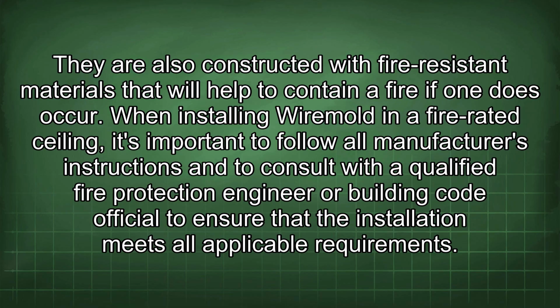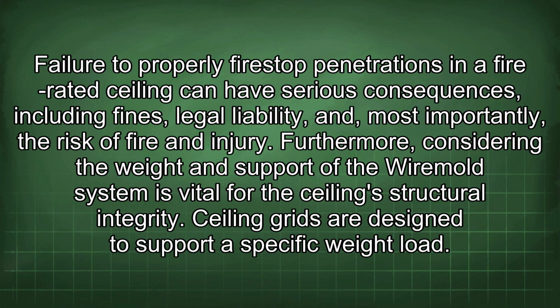When installing Wiremold in a fire-rated ceiling, it's important to follow all manufacturer's instructions and to consult with a qualified fire protection engineer or building code official to ensure that the installation meets all applicable requirements. Failure to properly fire stop penetrations in a fire-rated ceiling can have serious consequences, including fines, legal liability, and, most importantly, the risk of fire and injury.